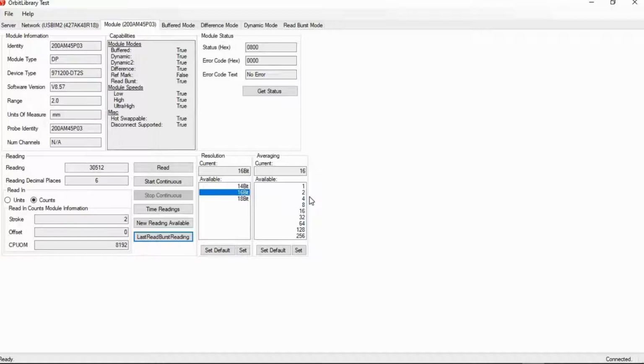To explain averaging, we need to explain the function of the digital probe and its module a little bit more. Basically, the Orbit module takes an electronic signal from the probe, which goes through an analog to digital converter. The sensor signal is on a high-frequency carrier and is first extracted from this. But this process requires an analog aliasing filter before the signal is passed to the A to D converter. This is to prevent higher frequencies from coming through and creating false data.